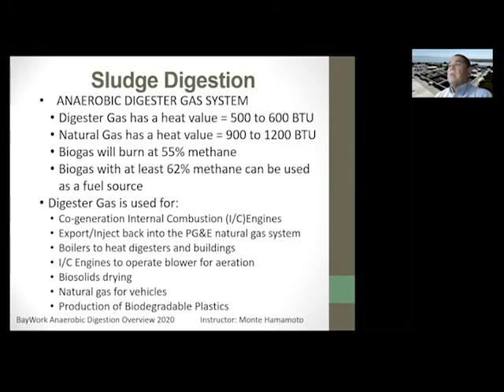So digester gas, we use it for cogeneration. We have big engines, Jenbacher engines that turn GE generators, and we can produce 1.2 megawatts of power that we use to sustain our treatment plant. And now we have just got the ability to export power. If we produce too much, we can actually put it back out on the PG&E grid. We also just installed 1 megawatt of battery storage. So we can use this power that we're generating from burning the digester gas or the biogas, and we can use that energy to recharge the batteries.